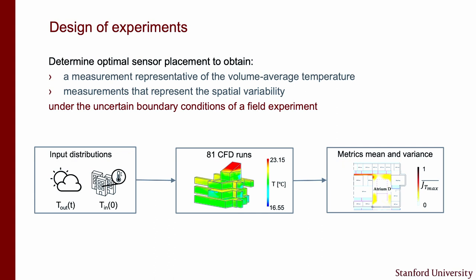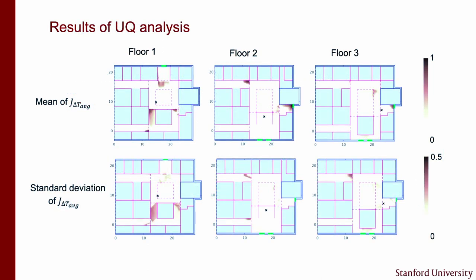I'm not going to go into the details of how we define the metric, but these plots show you this: high values here mean strong deviations of the average temperature, and high values here mean a strong difference in the metric depending on the outdoor conditions at the time. So you want to put your sensor where both of these are low, because that means that under all possible conditions we're going to have a really good representation of the volume average temperature.